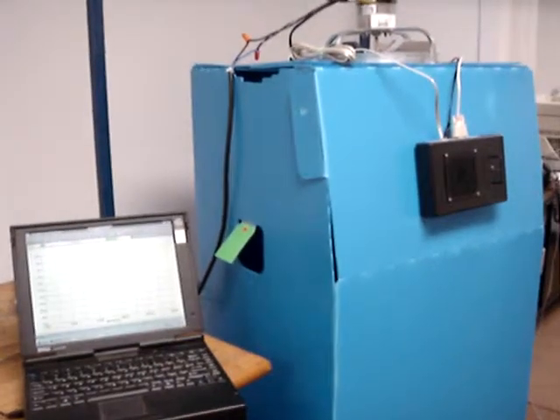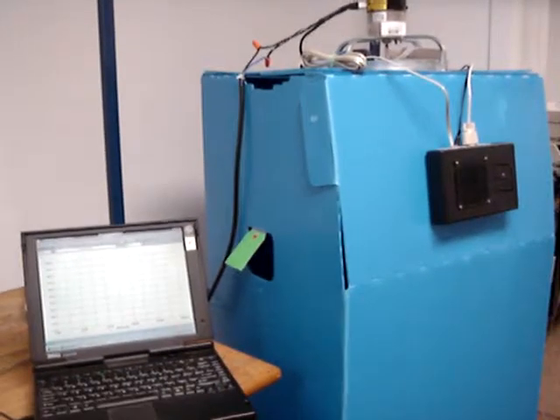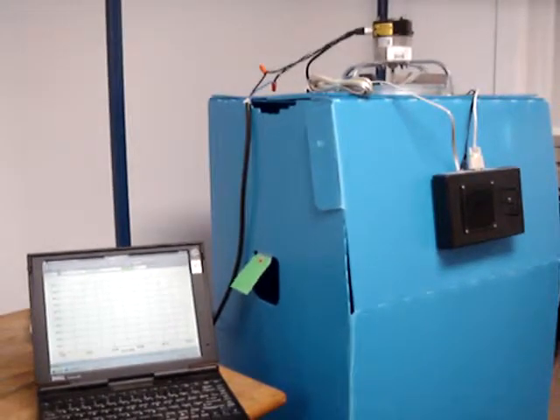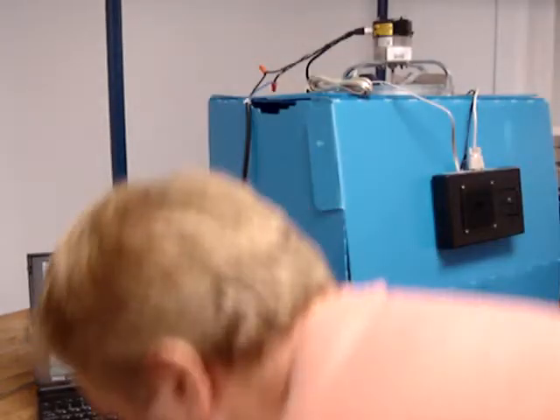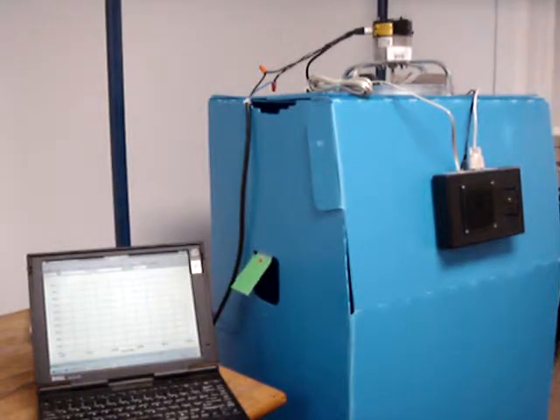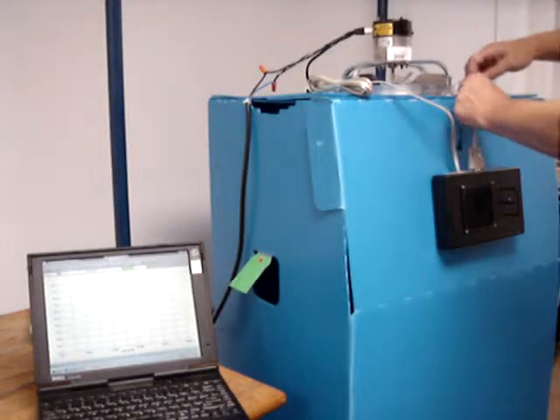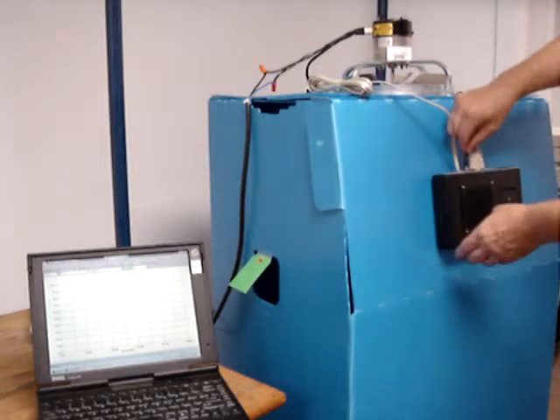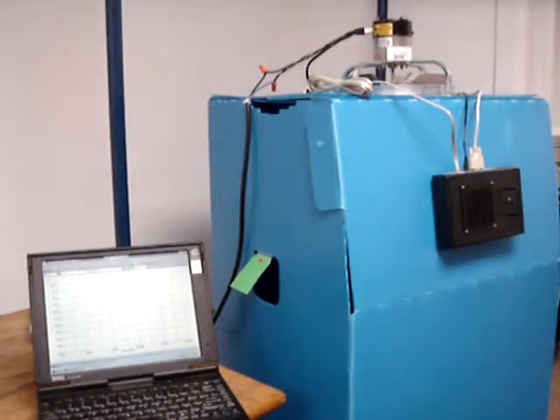So let me get this all running here. Just set this up. So I'll plug in the heaters for the server. It's about 1,000 watts of heat, and the fan generates anywhere from 100 CFM to maybe 500 CFM, again simulating the servers. Plug in the power to the CFM sensor, and that'll activate the fan, the exhaust fan.